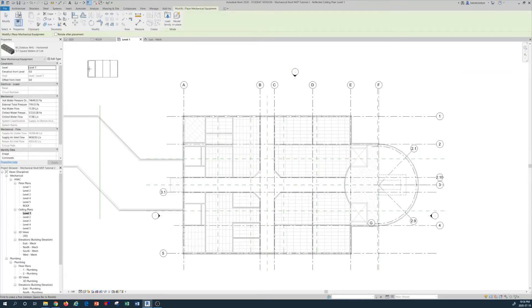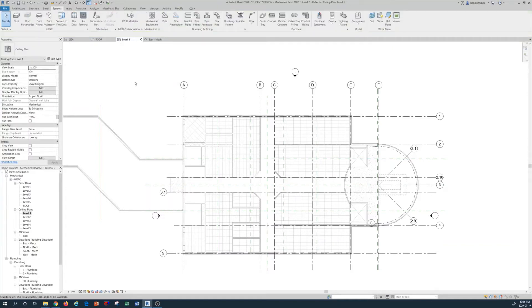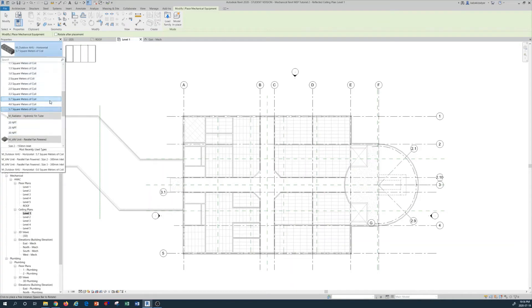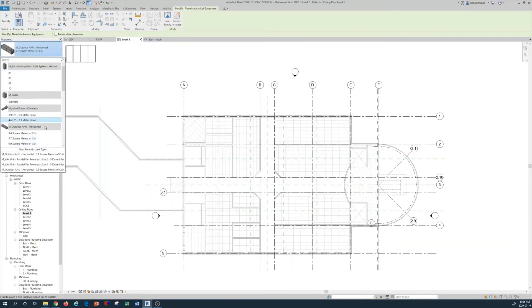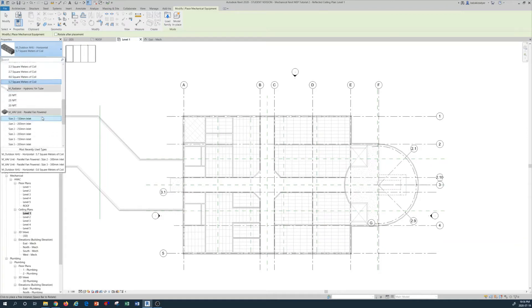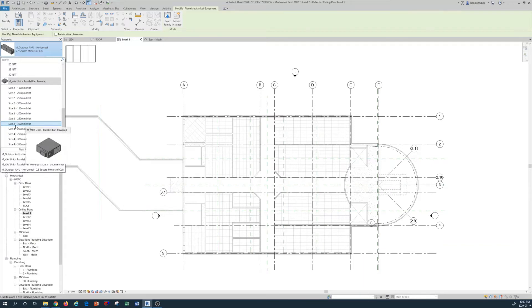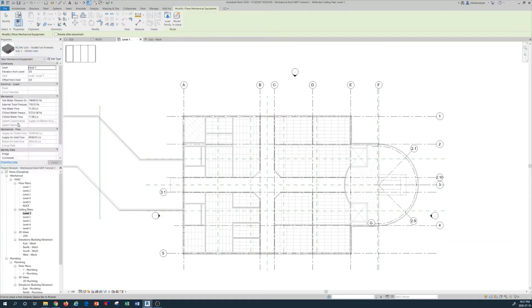To add terminal units or VAV boxes, I press Escape to exit the current selection, then go back to mechanical equipment in the properties bar. I scroll through the families to see if any VAV units are already loaded — I can see a VAV parallel fan powered unit. For this example I select size 3, 300 millimeter inlet, and left-click to select it.